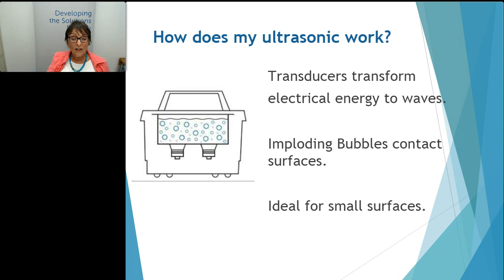But that does have implications because if imploding bubbles are how your device works, that means that you really have to make sure that those bubbles are working. That means, number one, you make sure you have good, clean solution that you're starting with each day, that you degas, that is, get some of those extra bubbles out of the solution at the beginning of the day. Check your instructions on your ultrasonic on how to do that. And most importantly, you've got to keep items submerged. Don't overload, and make sure that the devices are under the liquid. The little bubbles cannot implode on something that's sticking up above the water. So don't overload and keep the items submerged.